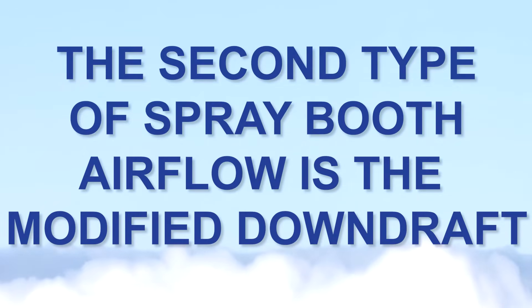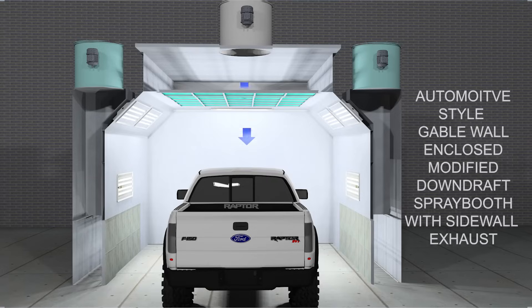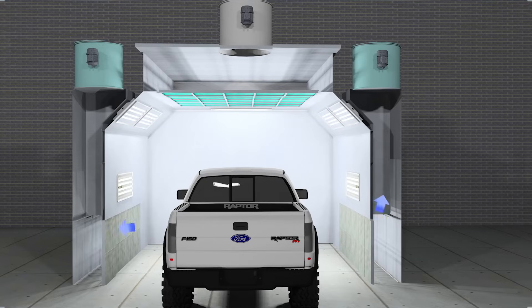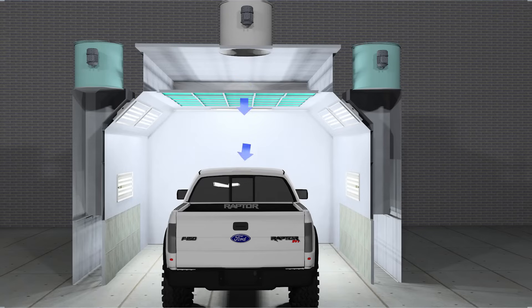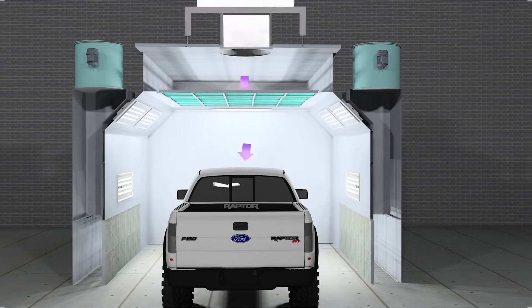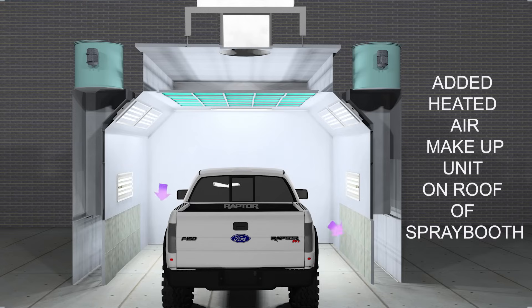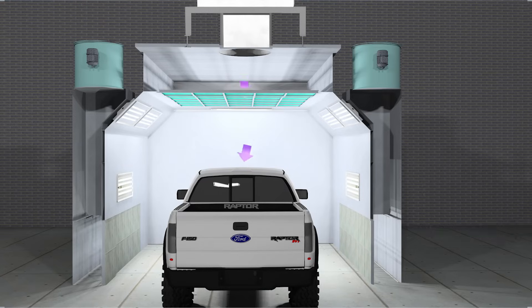The second type of airflow that you will see in a spray booth is the modified downdraft spray booth. It is very similar to the Crossdraft spray booth in every way, except the air does not come from one end of the booth and pass to the other end. It takes a shorter path from the roof or ceiling of the spray booth to the sides or back wall of the spray booth. This type of spray booth is more effective than the Crossdraft spray booth in contamination control. With a pressurized intake fan or heated air make-up unit, it will further reduce potential dust and other contamination from the incoming air passing to the exhaust filters.